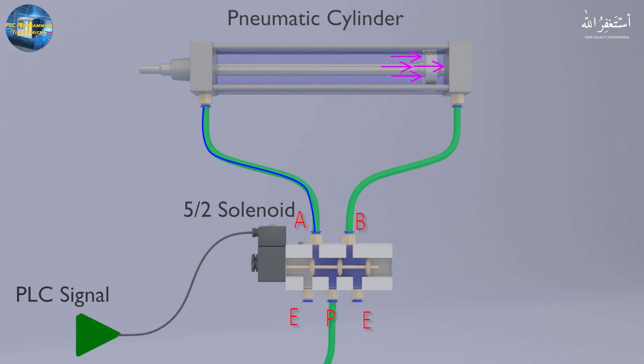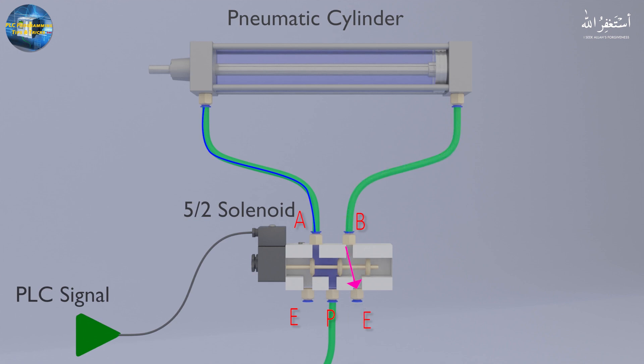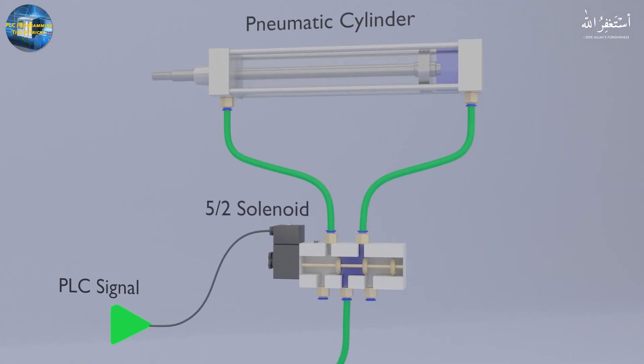Because of the force of the compressed air, the cylinder shaft moves backwards and gets fully retracted inside the cylinder body. The compressed air on the opposite side of the piston moves towards the solenoid through the pipes and gets exhausted into the atmosphere through port B, as port B is now linked with the exhaust port. This cycle of the solenoid valve turning on and off will continue as the PLC supplies signals to the solenoid valve.